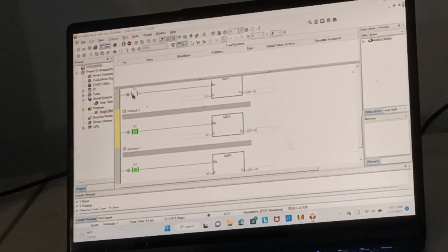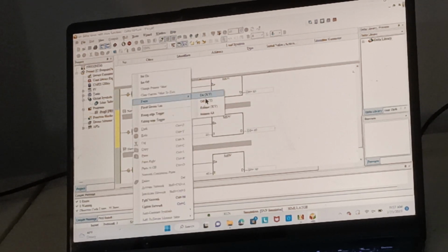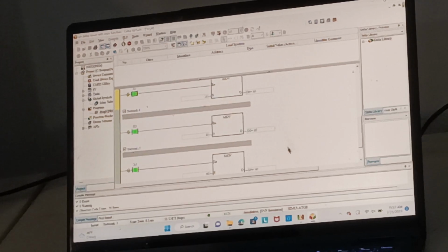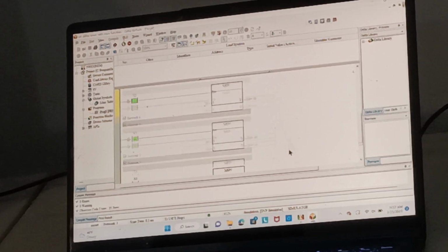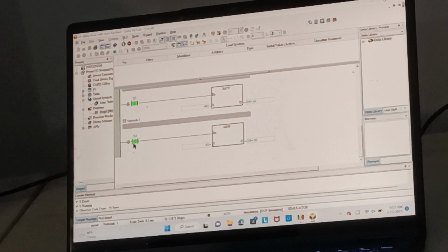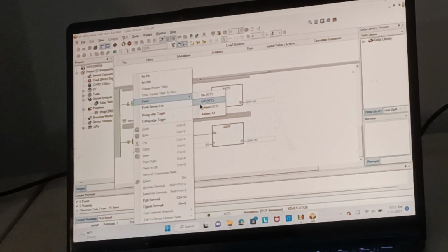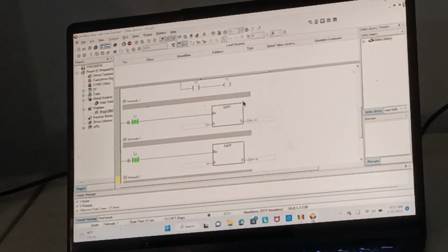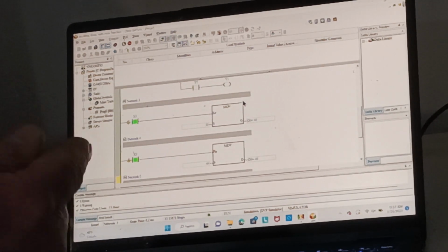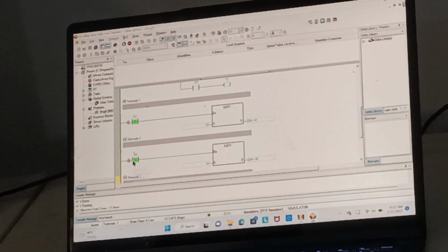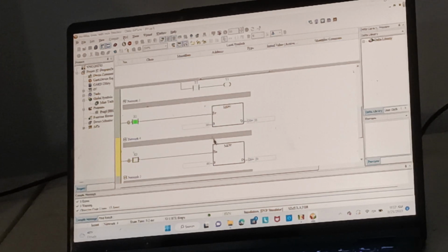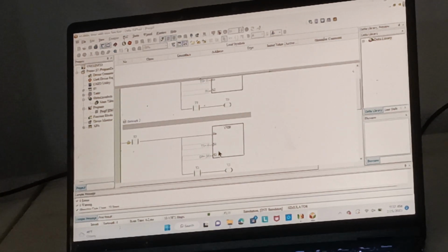So I could turn on every one of these move functions and it's still going to be 6 seconds because that's the highest value. Now, if I were to turn this one off, then the highest value now that's on is 4 seconds. So it kind of gets wonky if you have it on toggle switches. That's why you want push buttons. The last one you pushed is the one that it goes with, and that just makes life a little bit simpler. But that was your basic on delay timer with a data register. Next, we're going to do an off delay timer with the data register.